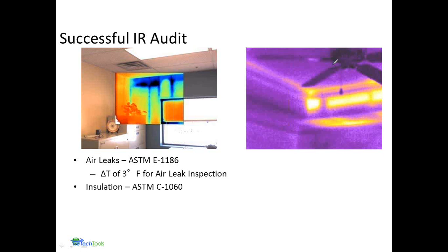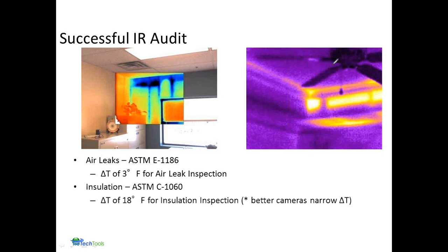When doing insulation checks, RESNET suggests at least an 18 degree delta difference. With a very good camera you can get by with less, but if it gets too small you won't see any difference or be able to interpret those problems effectively at all.